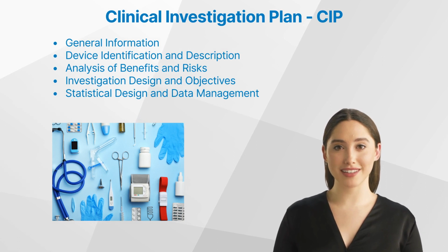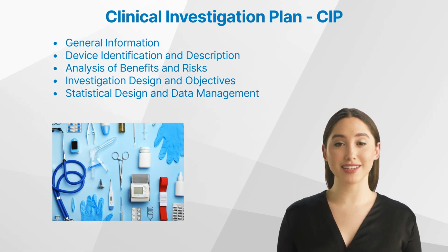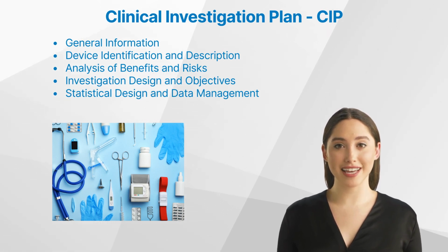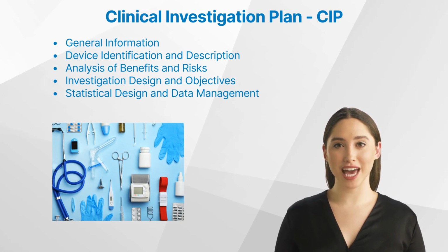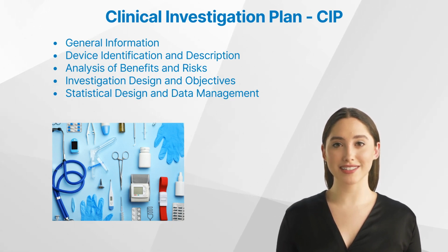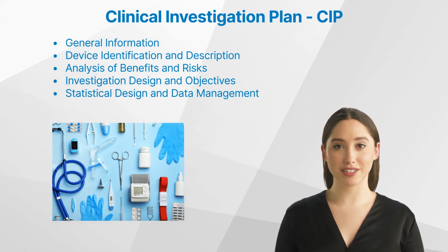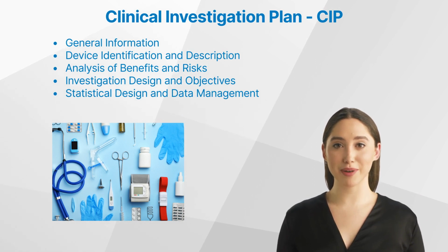Analysis of benefits and risks. Central to the clinical investigation plan, this section demands a careful assessment of the potential benefits against the risks. This analysis ensures the investigation is ethically grounded and scientifically valid, taking into account direct benefits to the study subjects and the broader implications for public health. This section should also identify all risks of participating in the study and lay out plans for risk mitigation.